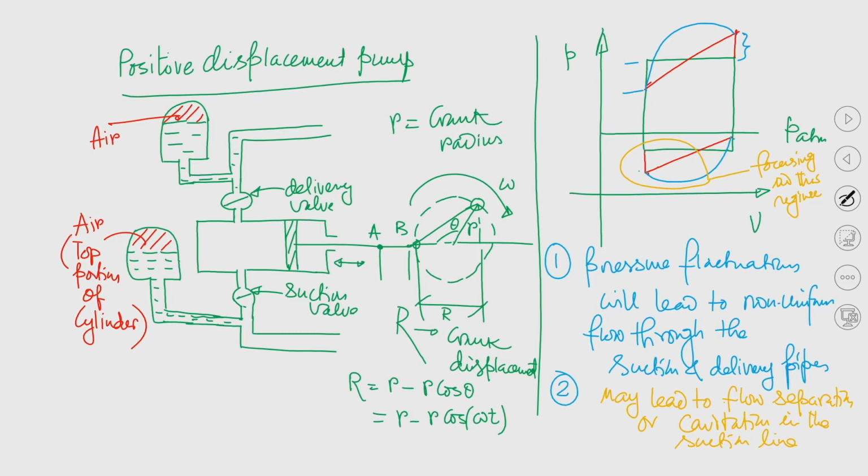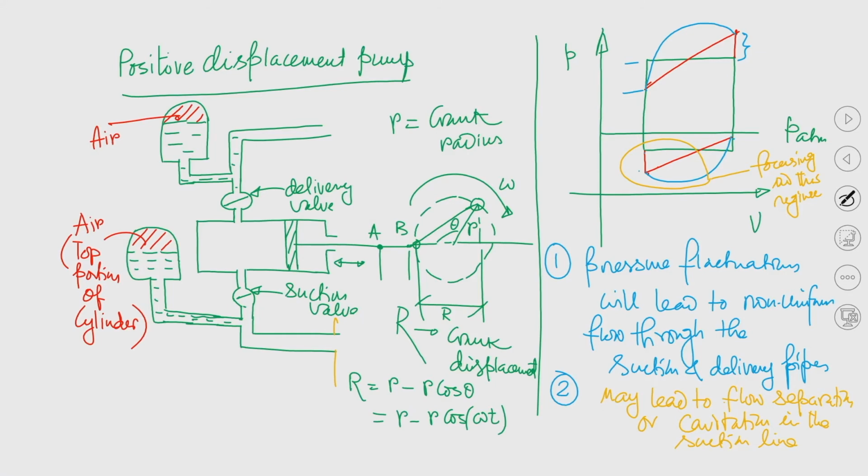So, in the suction line, what is done, try to understand. This is the suction chamber, right, and liquid is coming from the suction chamber. Now, when the piston is accelerating at the beginning of the suction stroke, pressure falls. On account of that significant pressure drop inside the cylinder, as we have discussed, liquid will try to move with a higher velocity through the suction pipeline into the cylinder.